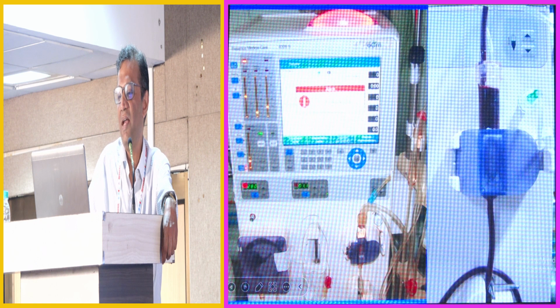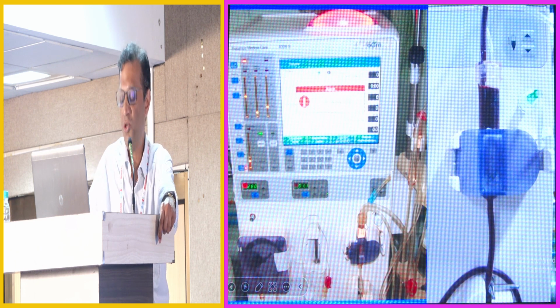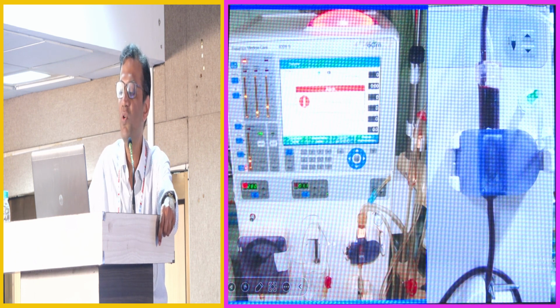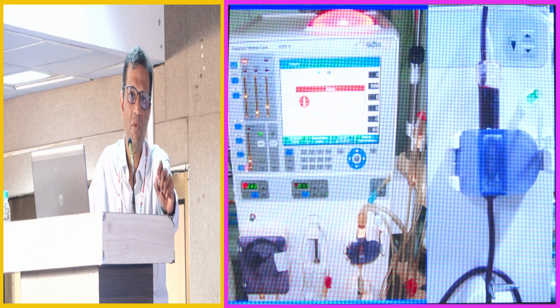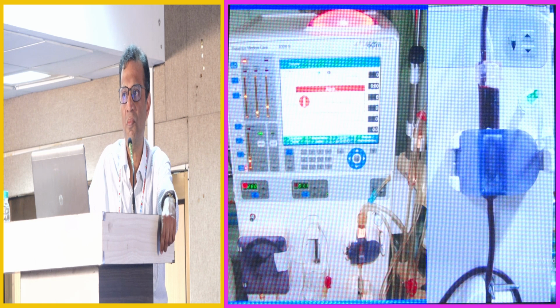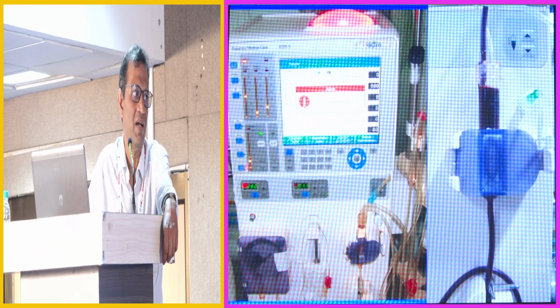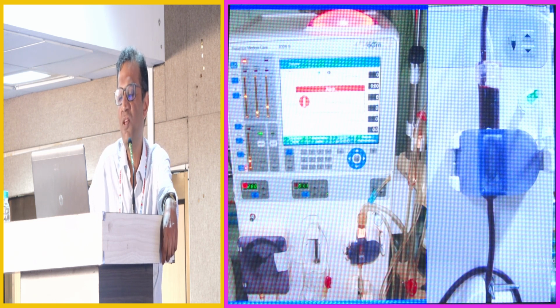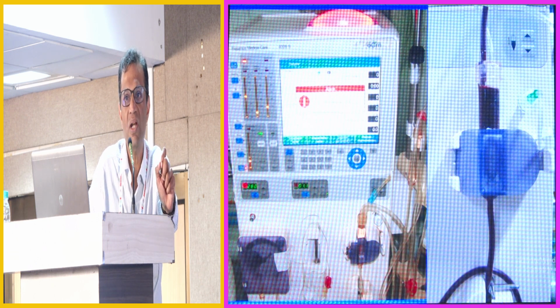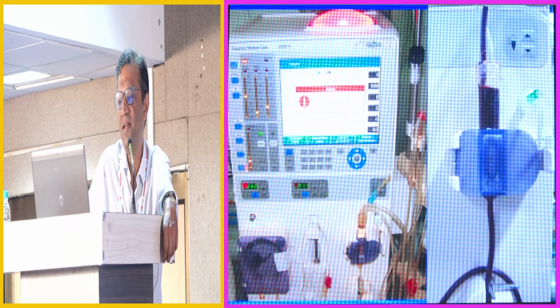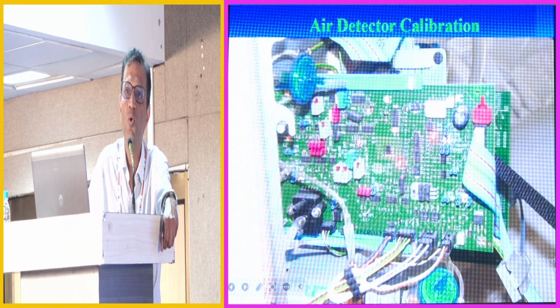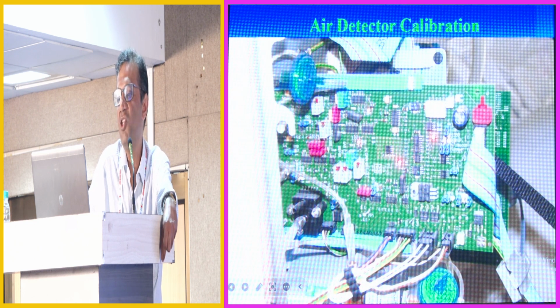Now here you can see that the air detector alarm is alarming. There's a red light flashing at the top of the machine, although the tubing segment appears to be nicely full of saline. So it shouldn't have given the alarm. Why does that happen? It happens because there is a wide variety of blood sets available for sale, and there is a wide variability. There isn't a standardization of blood sets. So when you change your blood set, if the newer blood set is narrower than the one being previously used, then a column of air might form between the detecting crystal of the air detector and the blood tubing segment, and that will give a false air alarm. To take care of that, we need to calibrate the air detector each time that we change our blood sets.